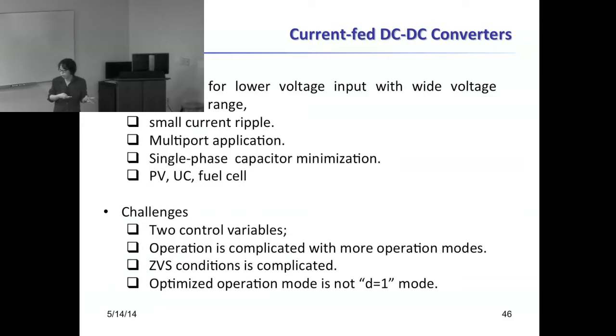The reason is it's suitable for lower voltage input with wide voltage variation range, and it can also provide small current ripple. The main reason is we have two control variables: duty cycle control and phase shift angle control. But the problem is the operation becomes much more complicated compared to voltage fed.